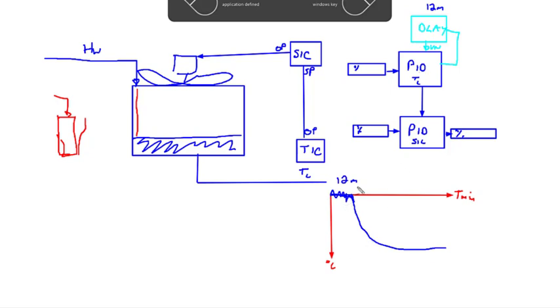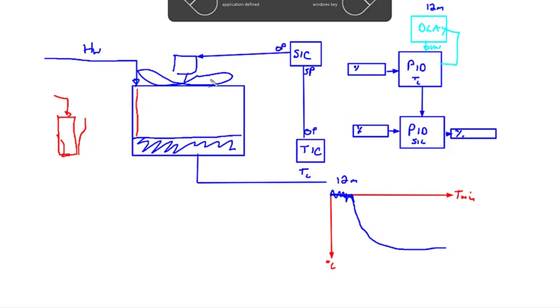It was working fine for a while up until later in the evening. What we found were problems around this PID because what was happening is between about 40 percent and 70 percent, or 40 and 50 percent, the speed of the machine didn't change. So it was this artificial dead band.